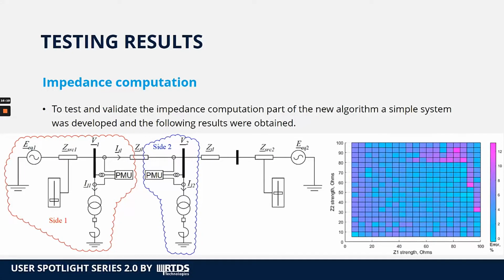In this system, multiple scenarios were run, and the errors of the impedance computation were investigated. The errors of the impedance computations are shown on the heat map on the right-hand side of the slide, and we can see that the impedance computation part of the algorithm produces an error of about 4% on average. In some edge cases, the error can go up as high as 12%. This was found to be sufficiently accurate for the out-of-step protection algorithm function. So we move on to the results of the out-of-step protection algorithm testing.